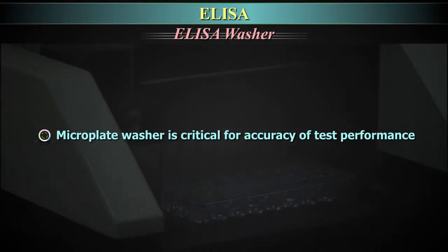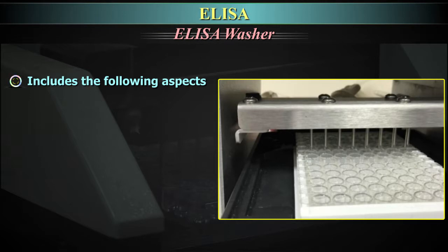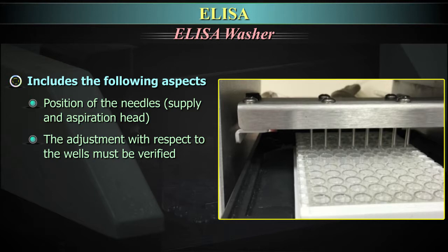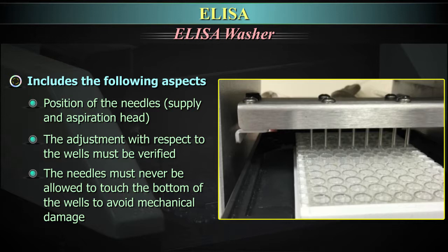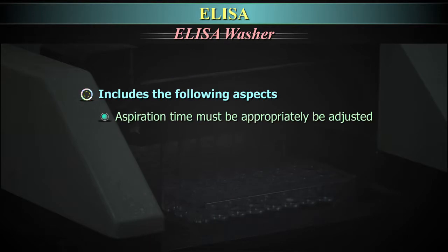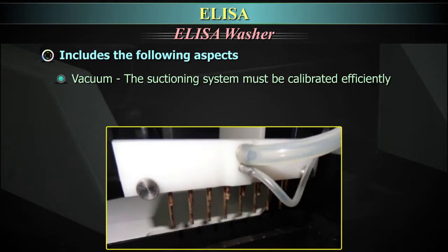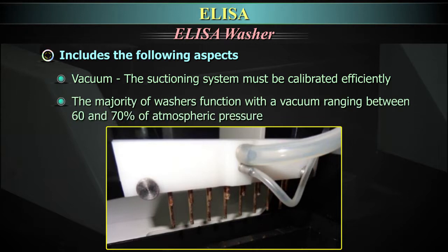ELISA washer. The microplate washer is critical for accuracy of test performance. Key aspects include: position of the needles, supply and aspiration head — the adjustment with respect to the wells must be verified. The needles must never be allowed to touch the bottom of the wells to avoid mechanical damage. Aspiration time must be appropriately adjusted, and the suction system's needles must be clean and free of obstructions. Distributed volume has to be calibrated. The suctioning system must be calibrated efficiently; the majority of washers function with a vacuum ranging between 60 and 70% of atmospheric pressure.